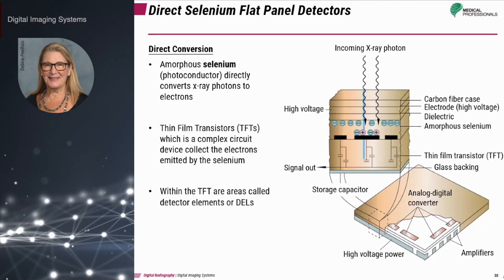The flat panel detector array is designed in layers. The top layer is a bias electrode, followed by amorphous selenium, then the thin film transistor array connected to the storage capacitors. The TFTs then read the signal and transmit it to a computer workstation. Thin film transistors form a photosensitive array of electronic components layered into a glass foundation, including the readout, the charge collector, and the light-sensitive elements.